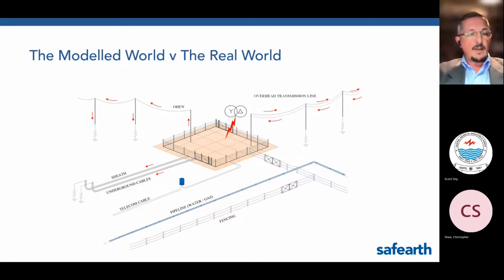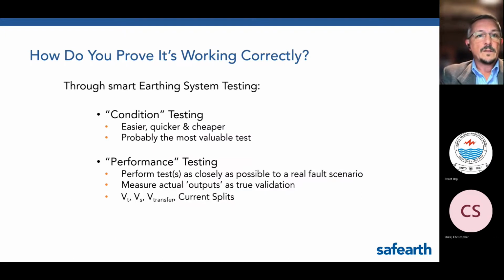And these methods now aren't high current and dangerous. They're actually safe, they're accessible, and they're affordable. So let's look at the categories of testing that the newer tests, in the last 20 or 30 years, tend to fall into. If we're trying to work out whether it's doing its job, we can think of assessing an earthing system in two categories of tests. One is condition testing, which is designed to quickly show if damage or deterioration or improper modification is present and that it now requires some kind of corrective action. Performance testing accurately and efficiently identifies actual electrical performance, but we'll talk a bit more about that later.